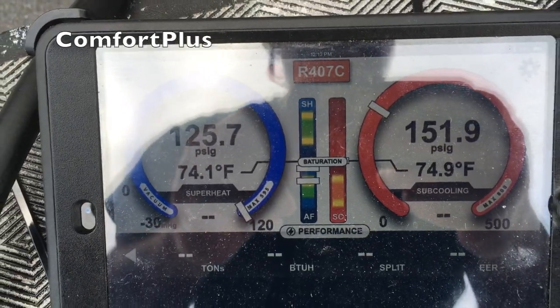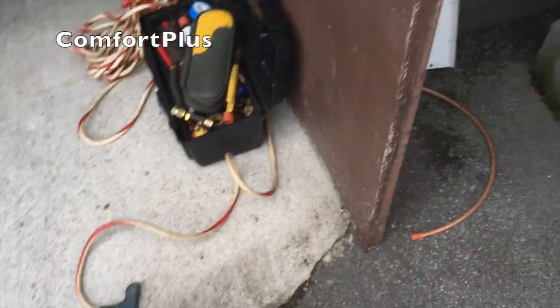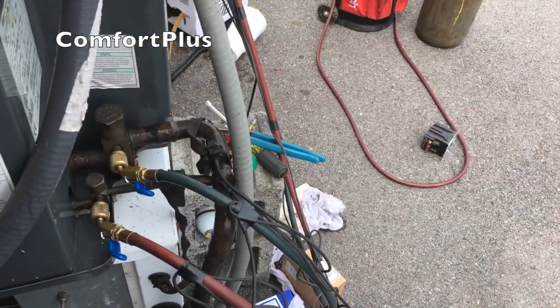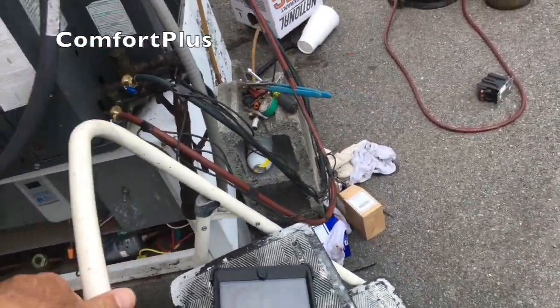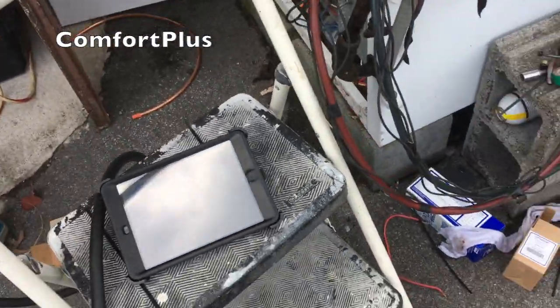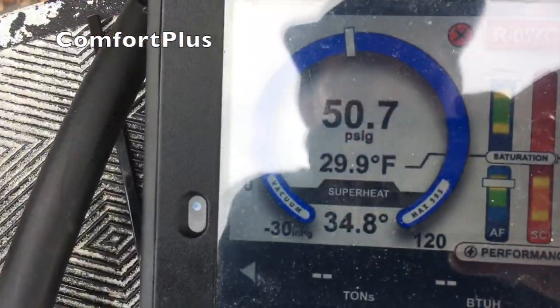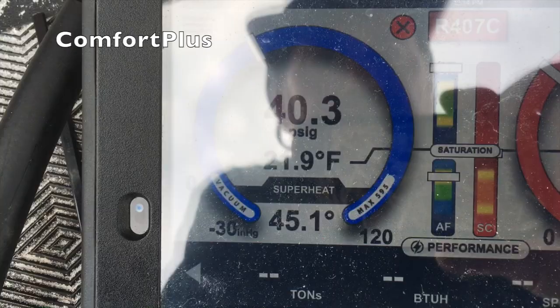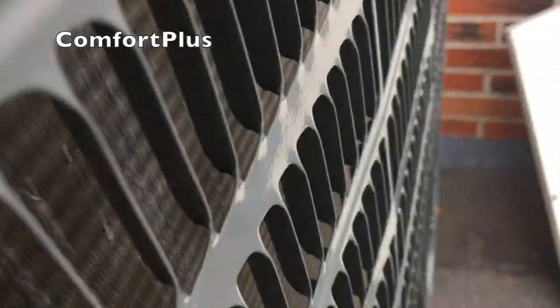Okay, got the gauge manifold connected here. He's turned the water on so it'll be circulating. Got to make sure it's pumping correctly. 3-phase. A 3-phase compressor can turn backwards, so you got to make sure it's actually pumping and not just churning. You can usually tell by the way it sounds. A lot of times it sounds like a box of rocks.